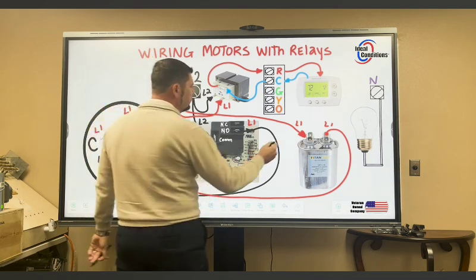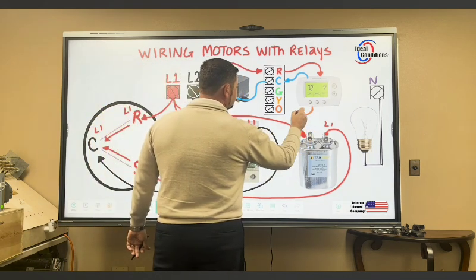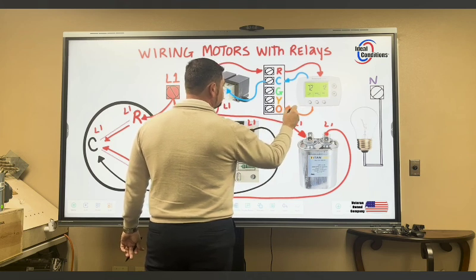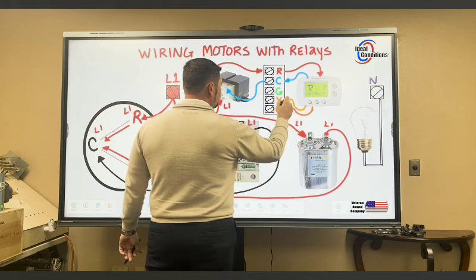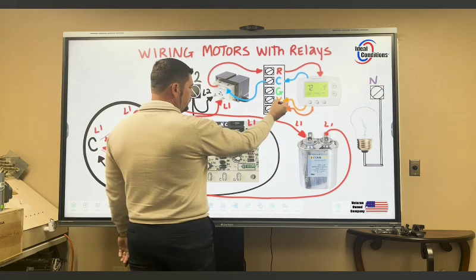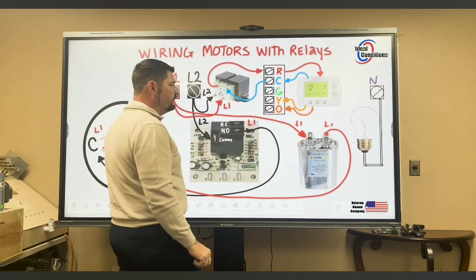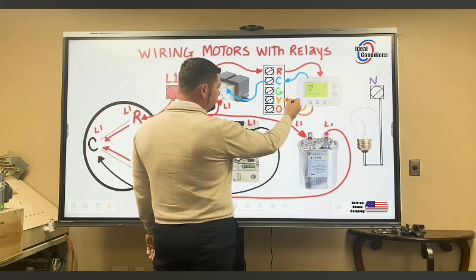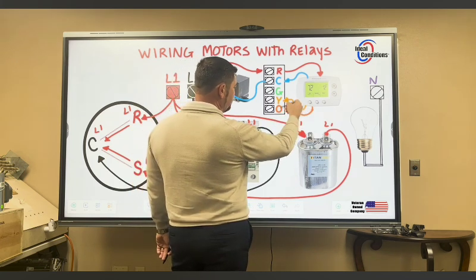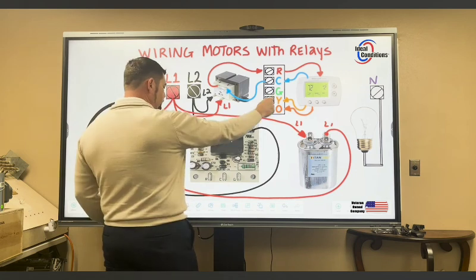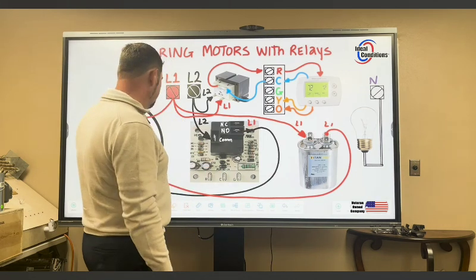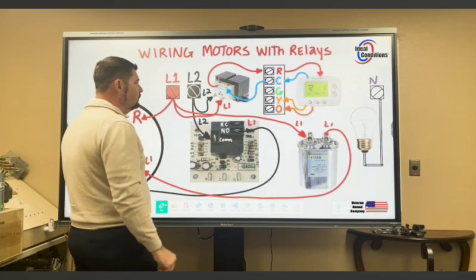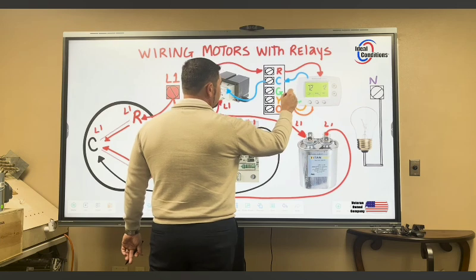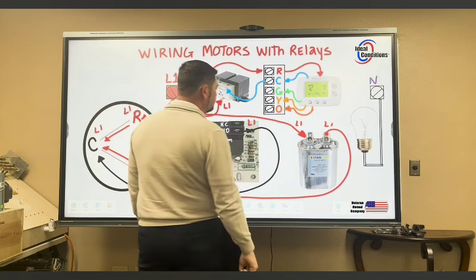We have Y and O. So we have our O call, which comes from the thermostat. We have a Y call that comes from the thermostat for cool, or if it's a heat pump, Y call by itself is for heat. Y and O if it's a heat pump, 24 volts on both of these if you want the heat pump to come on in cool mode.